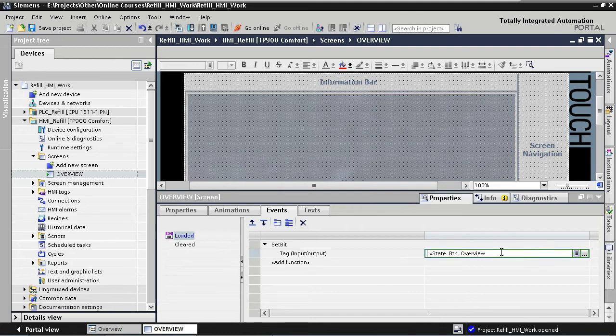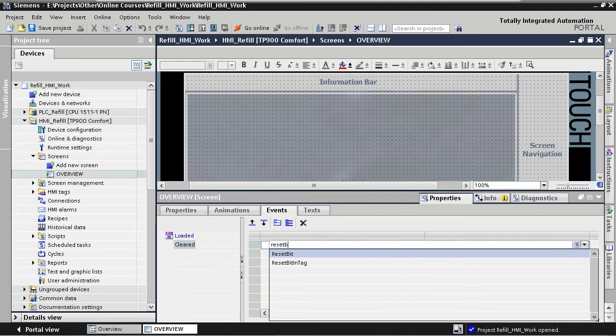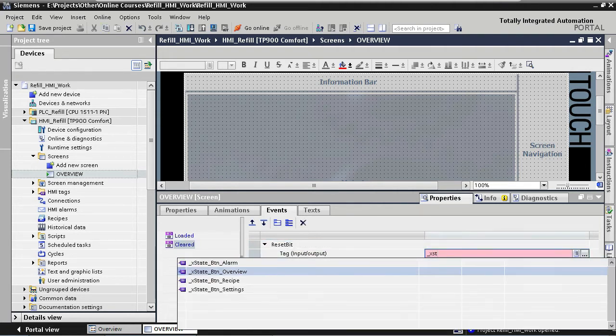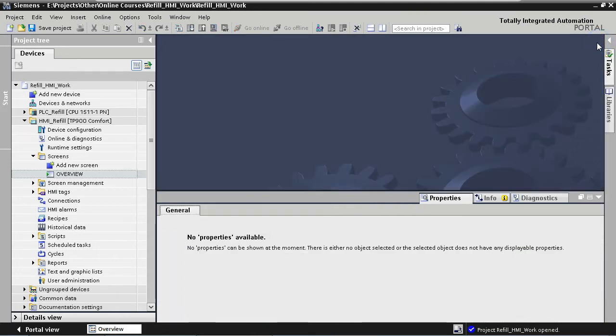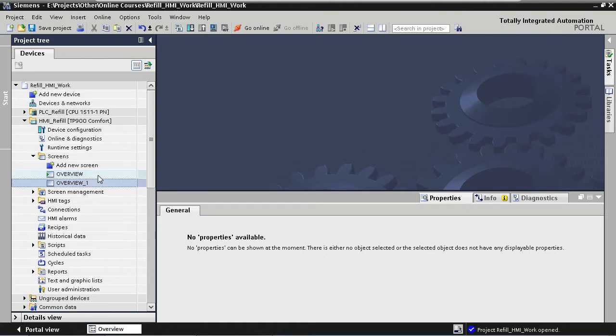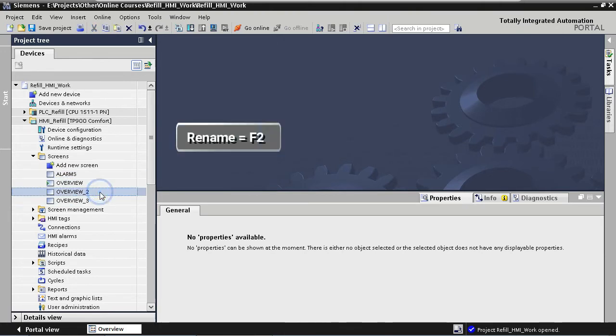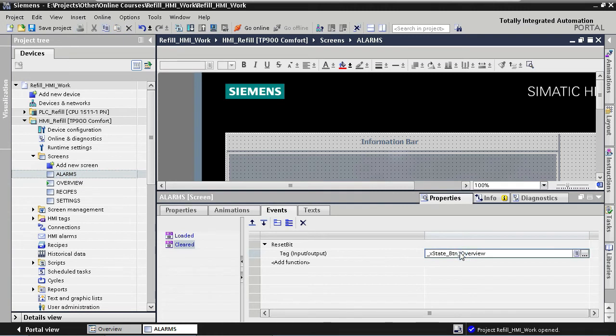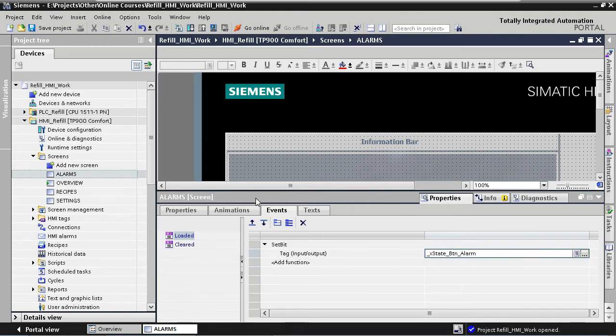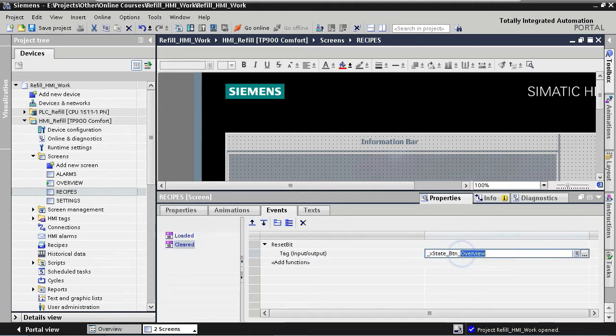When we clear the screen we need to write the value zero to that same tag. So we go to the Cleared event and add the Reset Bit function, then assign our tag. That's it for this screen. Now we copy the screen three times for our recipes, alarms, and settings screens, rename them, and then open each screen to adapt the loaded and cleared events with the corresponding state button tags for alarm, recipe, and settings.